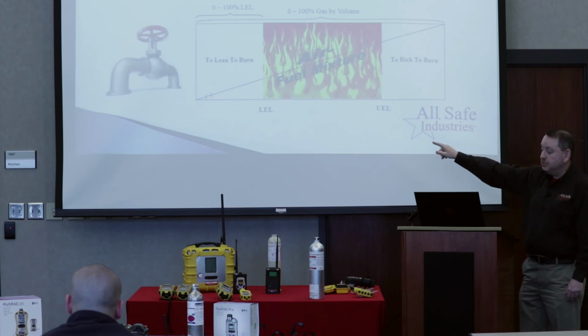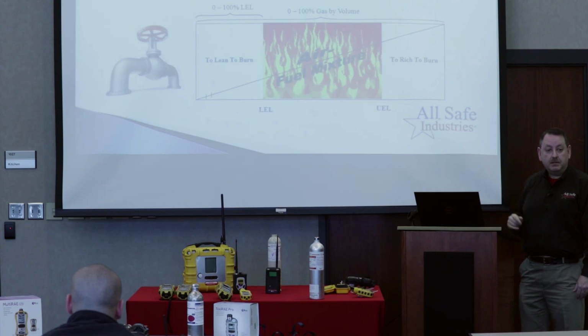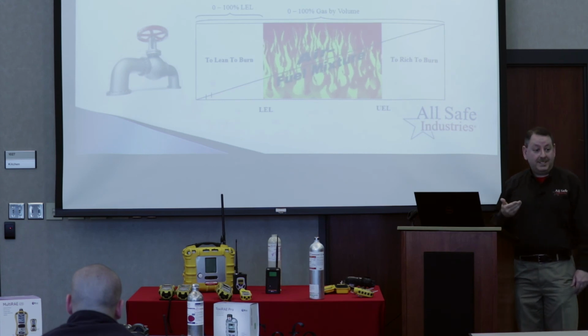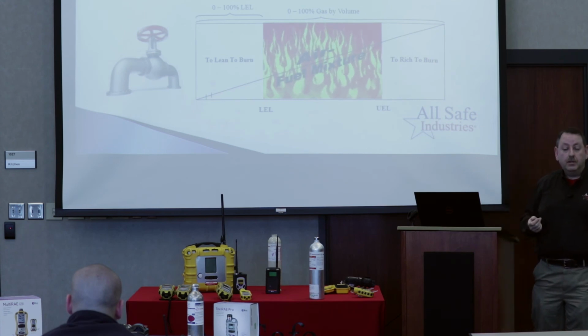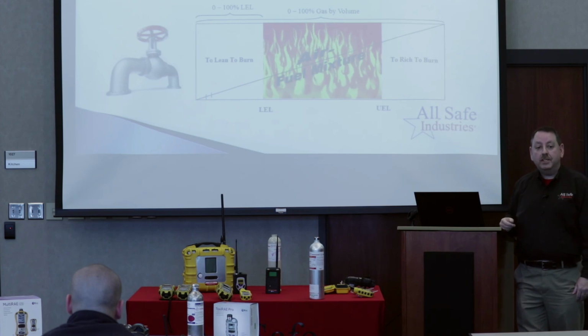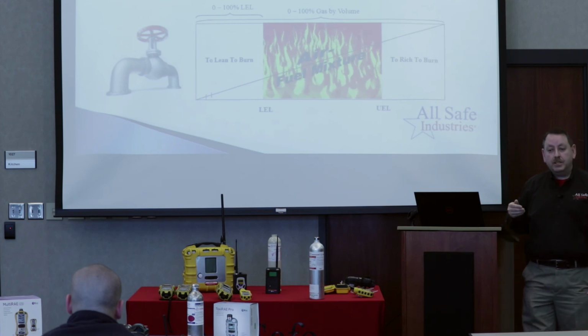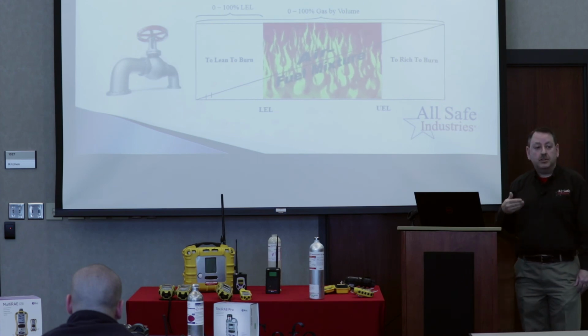And does everyone see the two little tick marks at the beginning of that diagonal line? That's where your sensor goes into alarm. So your first alarm will go off at 10% of the LEL. You'll get the second stage alarm at 20% of LEL. And we want to give you those alarms way in advance so that you can take proper precautions to either ventilate the space or evacuate the space or however you need to deal with the flammable gas being in an area where it shouldn't be.